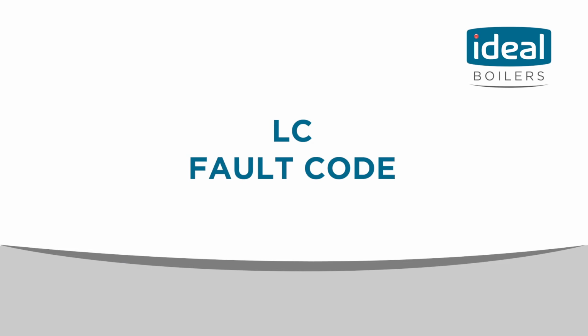If you encounter an LC fault code, it means that you have tried 5 restarts within 15 minutes. Isolate the mains power to the boiler, leave it off for a few seconds, turn it back on. If the fault code persists, contact Ideal Boilers.